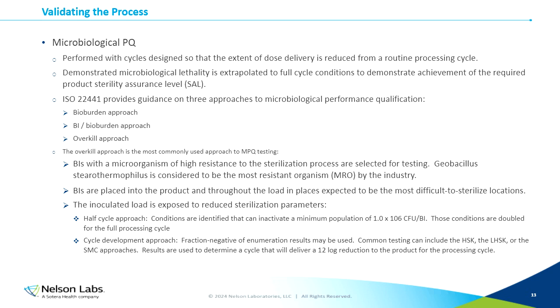Those may be areas like lumens, crevices, mated surfaces, etc. They could be other areas as well. The inoculated load is exposed to reduced sterilization parameters, as mentioned above. We have two main approaches that we use when we're working with overkill sterilization. The first is what we term the half cycle approach. We identify conditions that can inactivate a minimum population of 1.0 times 10 to the 6 CFU. Once we identify those conditions, they are doubled for the full processing cycle.